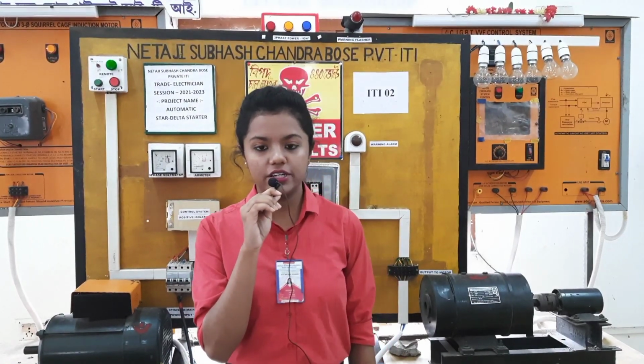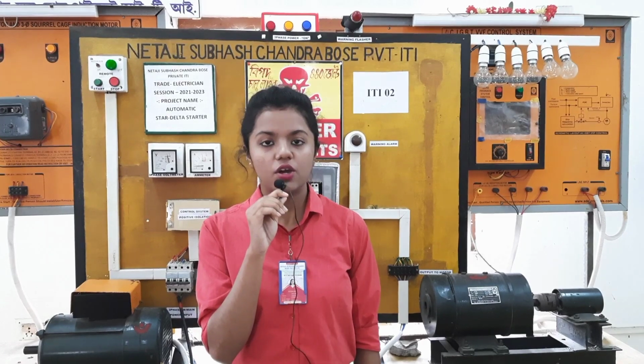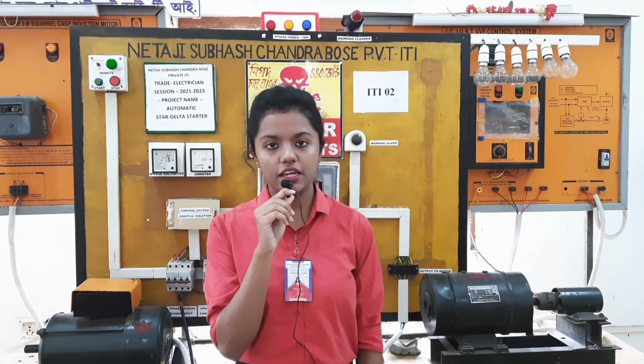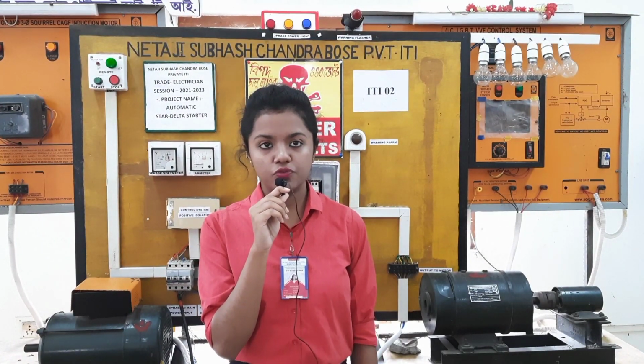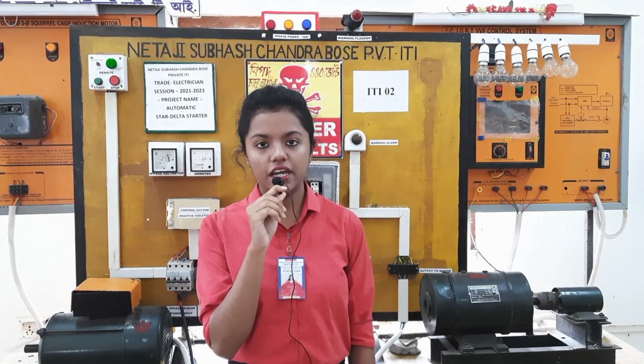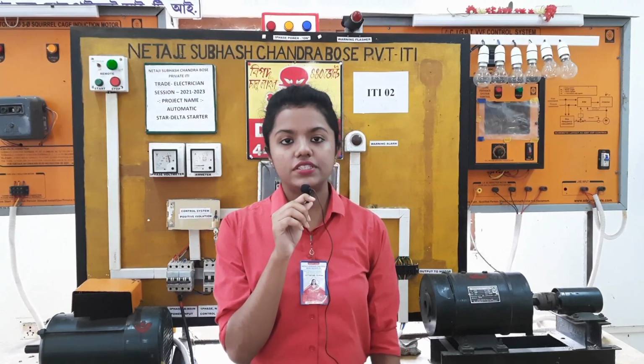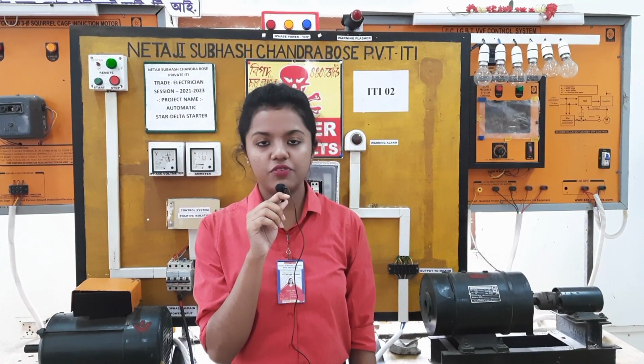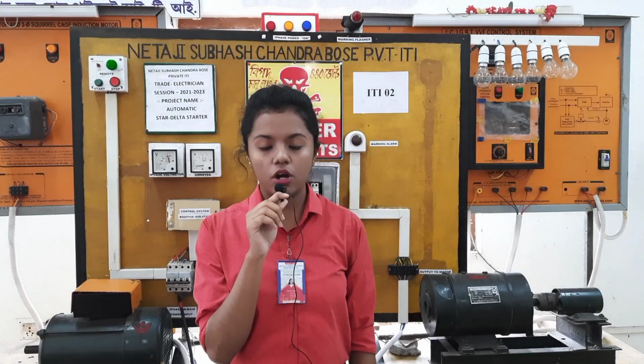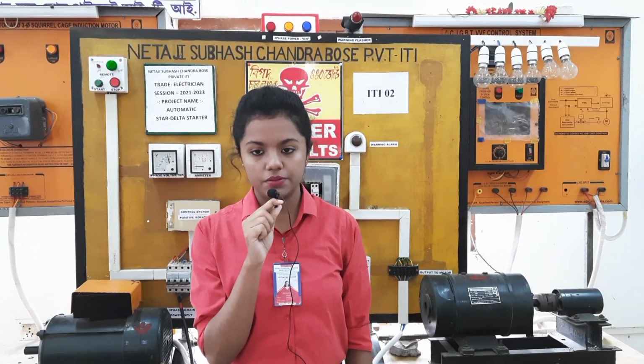Introduction of our project. A starter is a device which is used to start and stop the motor with overload and single phasing protection. Generally, three types of starter are used for a three-phase squirrel cage induction motor. That is direct online starter, which is used up to 10 HP motor, star delta starter, which is used for 10 to 25 HP, and auto transformer starter, which is used above 25 HP motor.